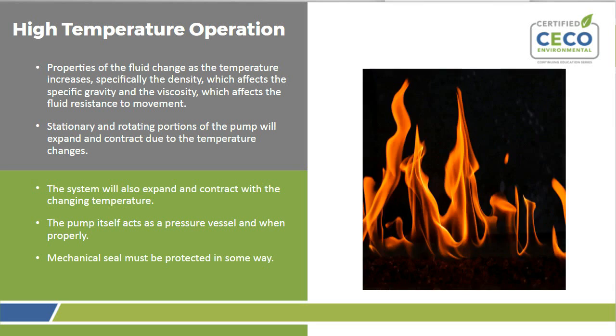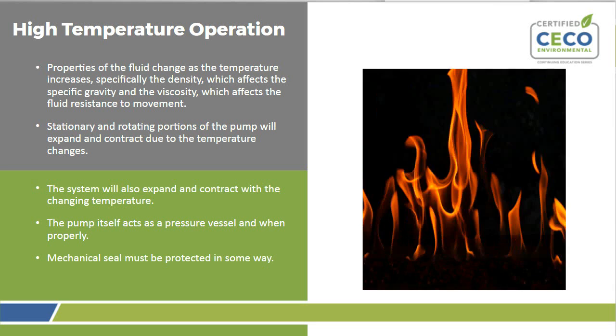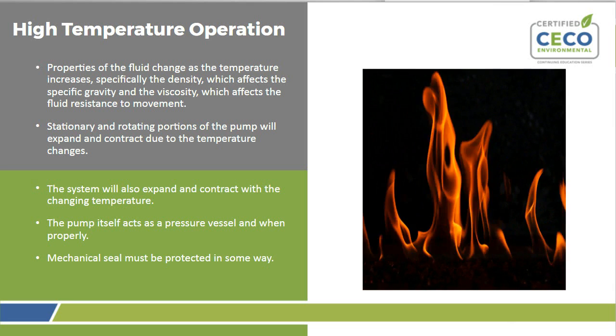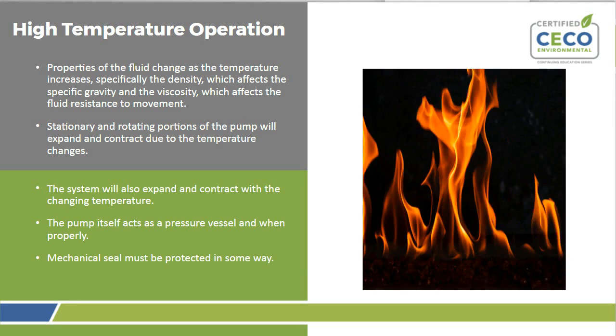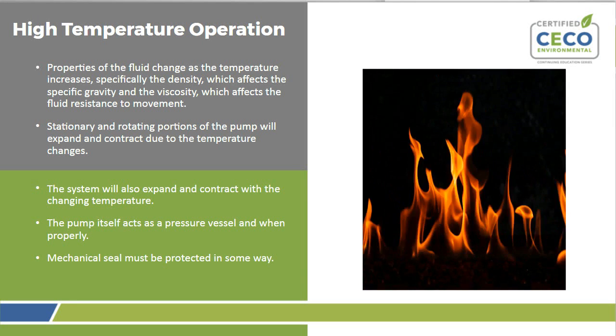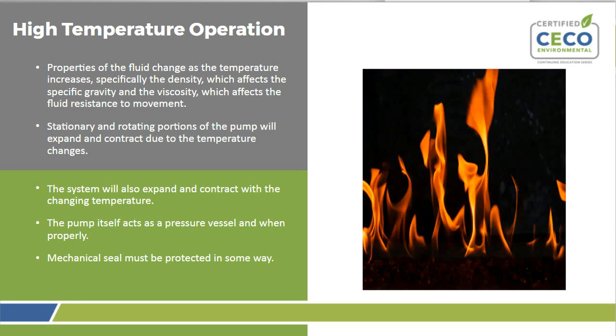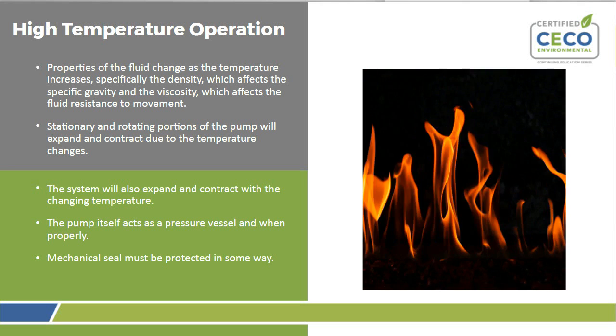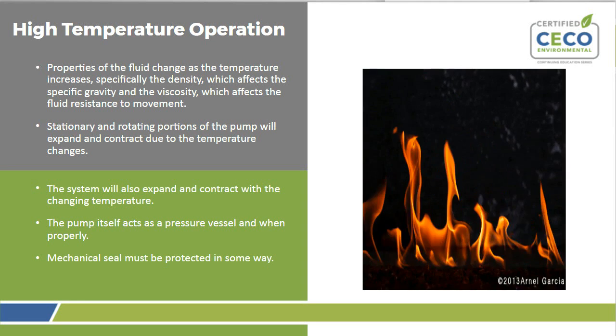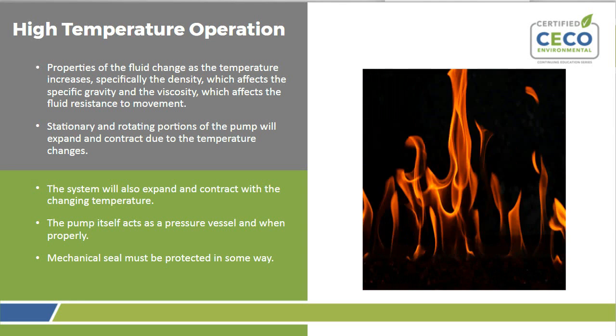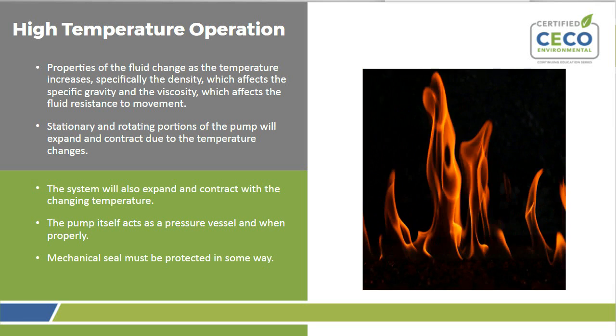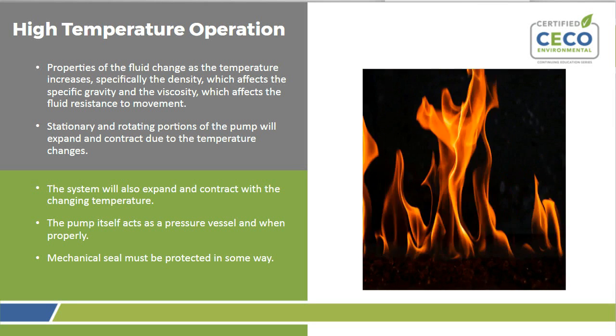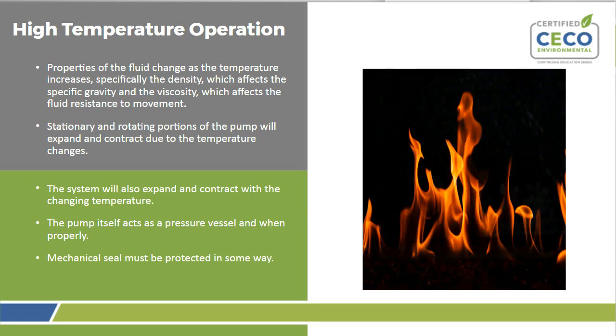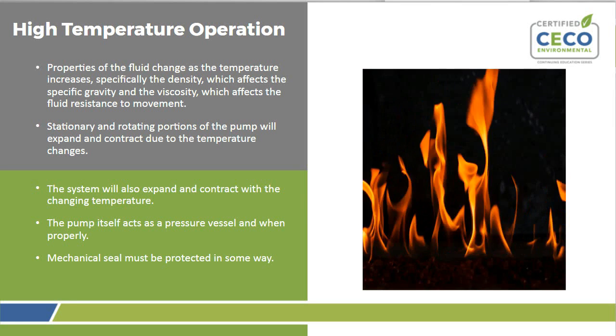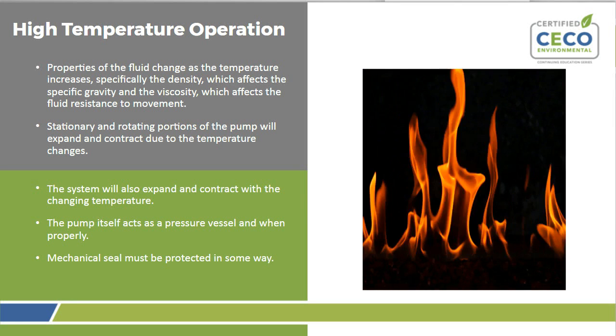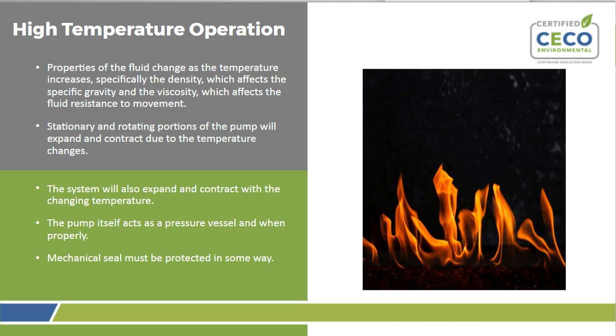Several aspects of the applications must be taken into consideration. First, the properties of the fluid change as the temperatures increase, specifically the density, which affects the specific gravity, and the viscosity, which affects the fluid resistance to movement. Stationary and rotating portions of the pump will expand and contract due to the temperature changes within. So these considerations have to be taken in during the design phase of the pump itself, that this pump is going to expand and contract and still do its job, and the rotating portions cannot be contacting the stationary portions while this happens.